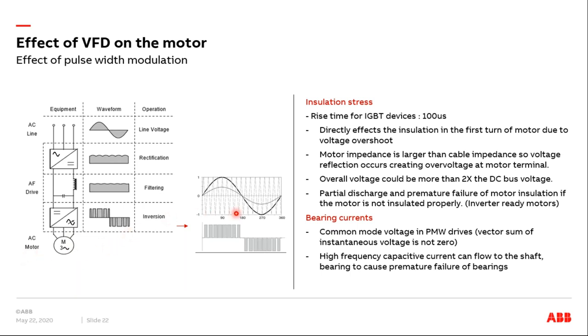We are using this really high pulse width modulation, which is basically switching, having these short square wave pulses, as you see in this figure, operating mostly in the range of 4 to 8 kilohertz in most industrial applications. One effect is due to the rise time of the IGBT devices used in the drive, but the other is because of the difference in impedance between the drive and the motor, because our motor has a high impedance, and then you have a transmission line and the drive, which has a low impedance.